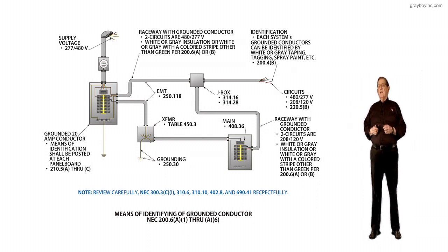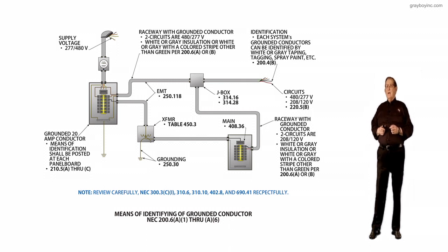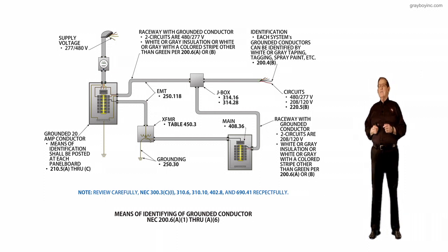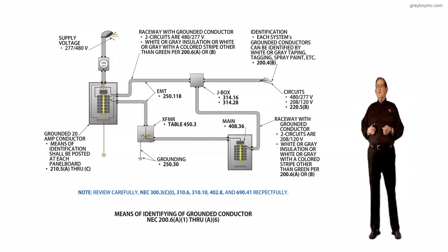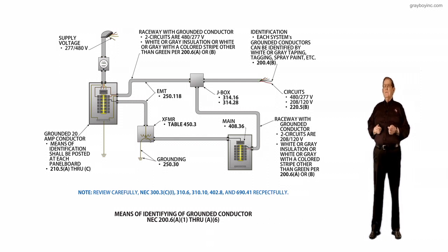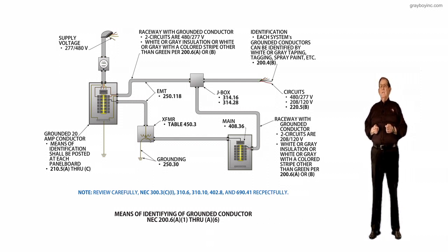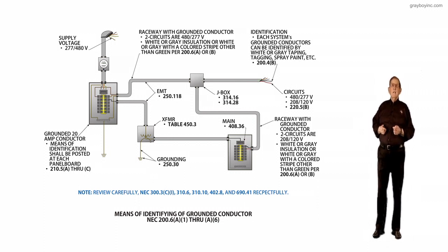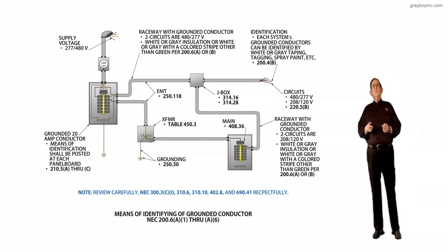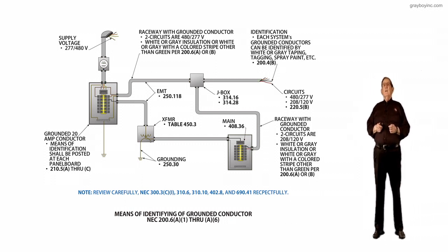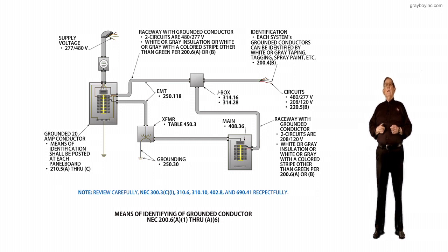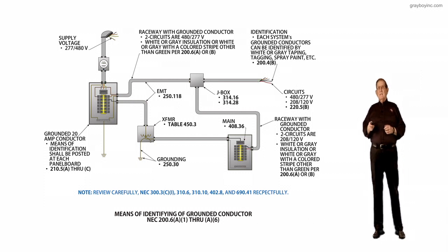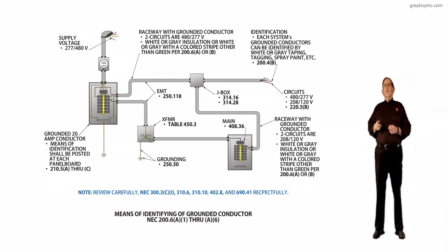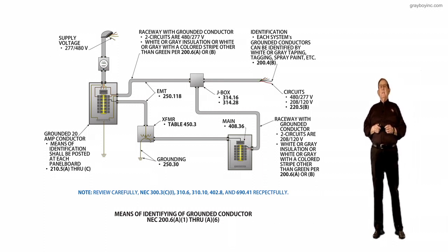Raceway with grounded conductors: two circuits are 208 volt, 120, white or gray insulation, or white or gray with a colored stripe other than green per 200.6A or B of the NEC. Thirdly, let's look at the raceway right next to the weatherhead. Raceways with grounded conductor: two circuits are 480, 277 volt, white or gray insulated neutral, or gray with a colored stripe other than green for 200.6 A and B.